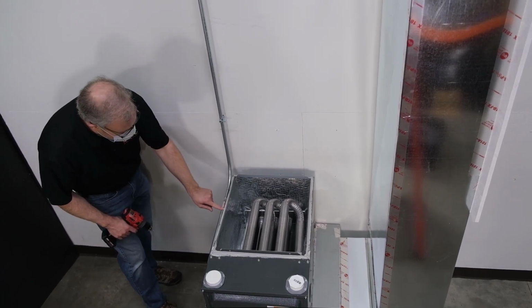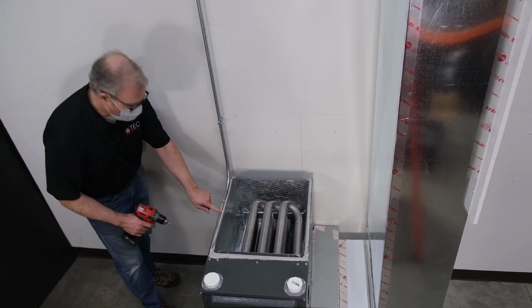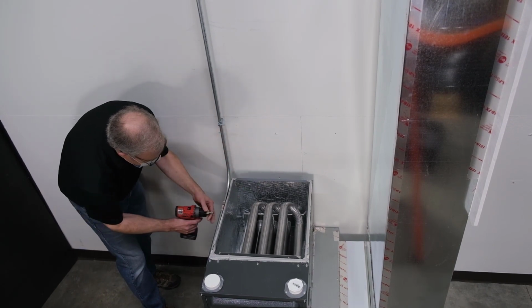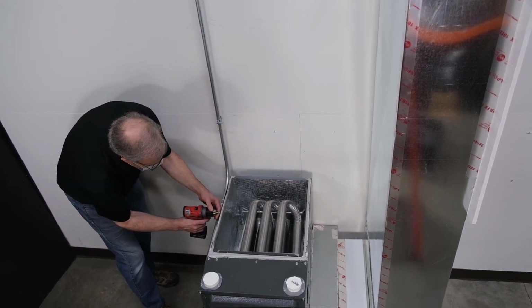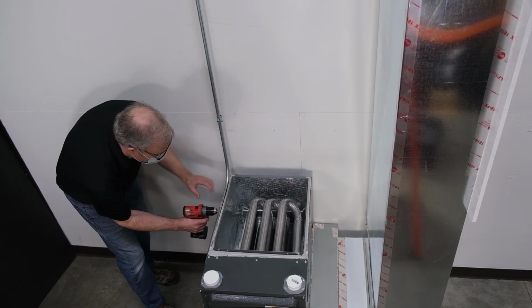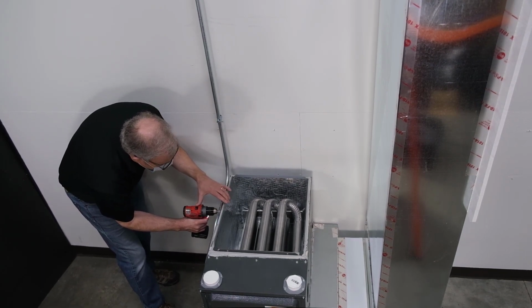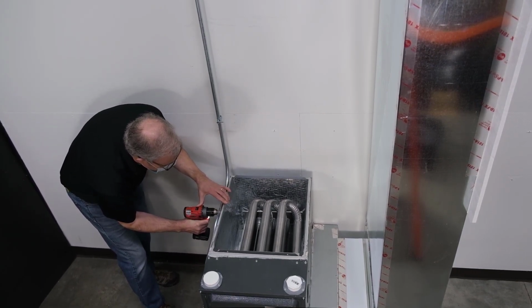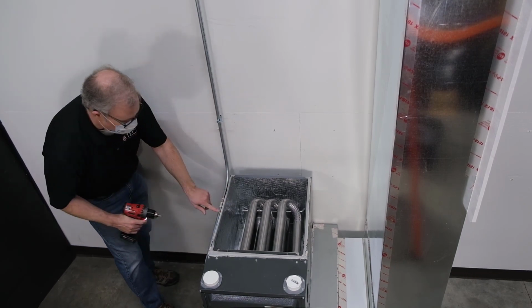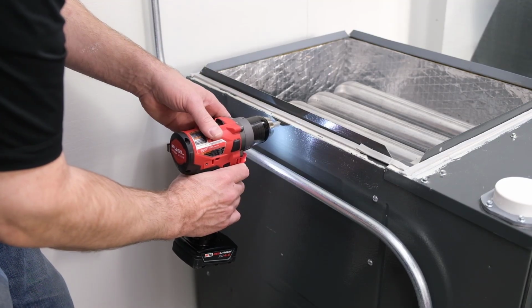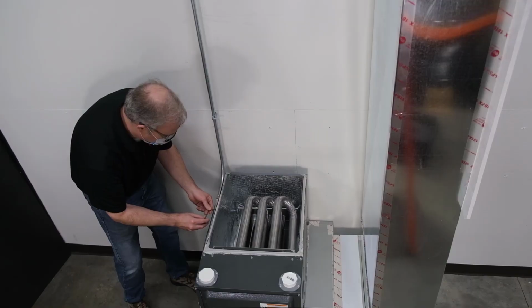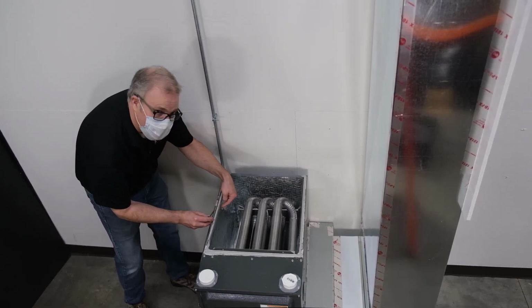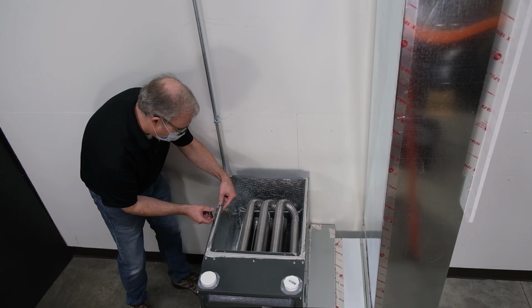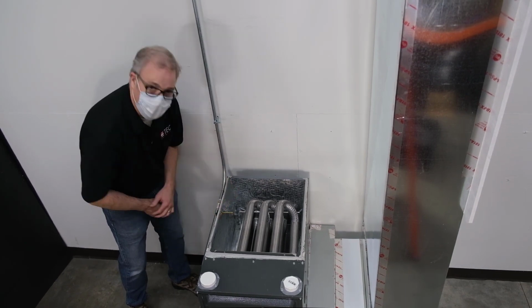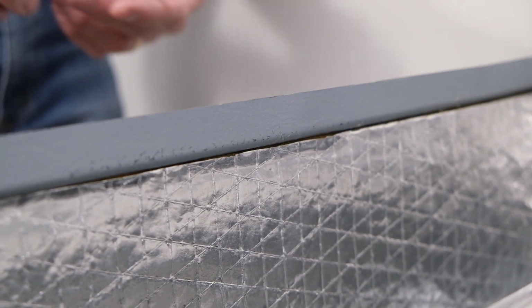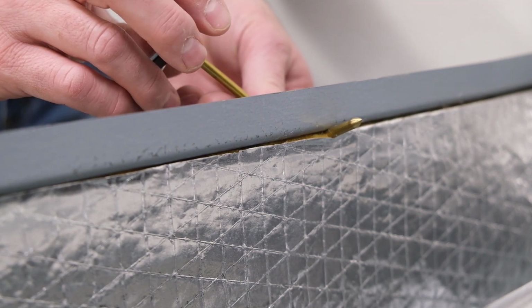So here Steve is showing you with that coil off so that you can see at the top of this furnace cabinet, there's quite a bit of space, and we're sure not to damage any part of the system. You always want to check to make sure, but typically this is going to be a safer spot. Now Steve is drilling right where that coil would mount, and here's a side view so that you can see he's right at the top. The other benefit of this location is that you can insert your static pressure probe up and over the top of the insulation provided by the OEM. Here's another view of that.